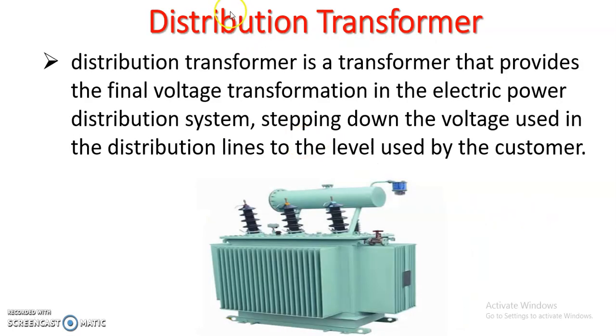The next equipment is a distribution transformer, which is the main component or main equipment of the substation. A distribution transformer is the transformer that provides the final voltage transformation in the electrical power distribution system. That means it is the final voltage conversion device that will step down the voltage used in a distribution line to the required value. That means it will step down the voltage to 400 volt, or in case of single phase it will take 230 volt. So this is the main part of this substation.